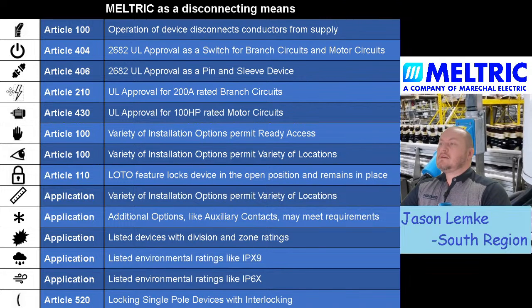The rest of these things are all like being rated for the amperage, being rated for the horsepower, within line of sight. We see a lot of this lockable disconnecting means as well, so I'll talk about some of the things that our device does in that area that can help you meet the requirements for a disconnecting means. But primarily, when we're talking about applications, what we want to be looking for is, does your disconnecting means require it to be a switch?